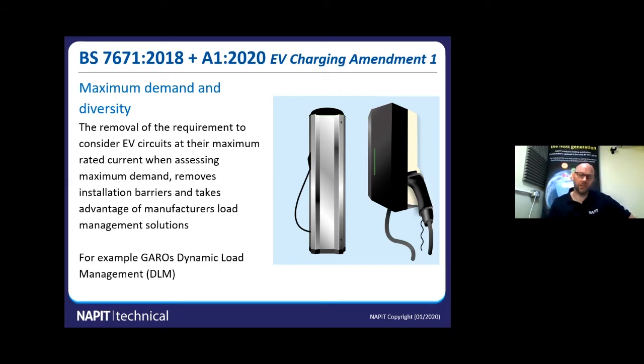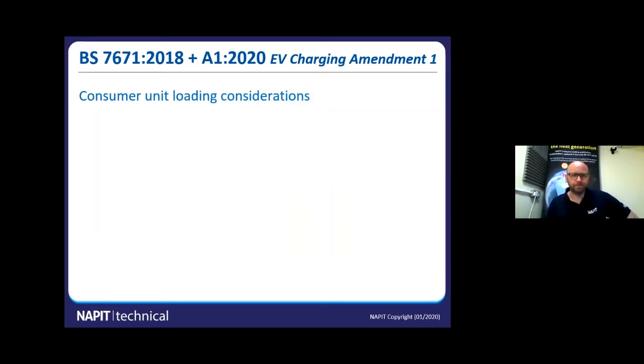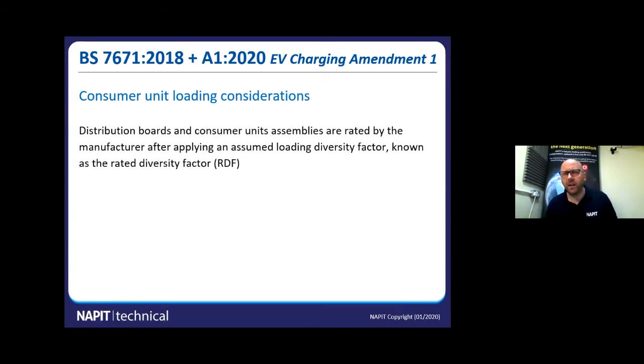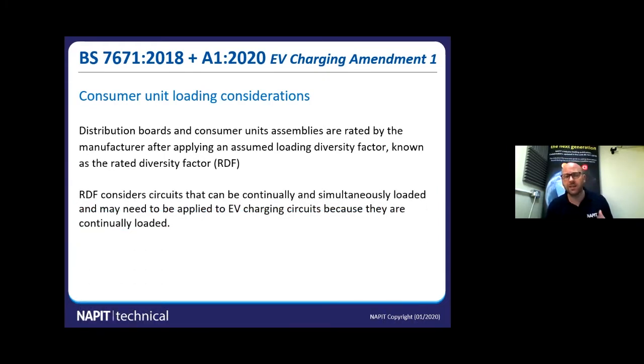That's fantastic. Excellent. Okay, moving on. So we're talking about these loading situations. Now, these next few slides have got nothing to do with Amendment 1. This is just some information that NAPIT wanted to bring to you regarding loading and consumer units. Distribution boards and consumer unit assemblies are rated by the manufacturer after applying an assumed loading diversity factor, which is known as the rated diversity factor, the RDF. Okay, and what it does, it considers what can be continually and simultaneously loaded.